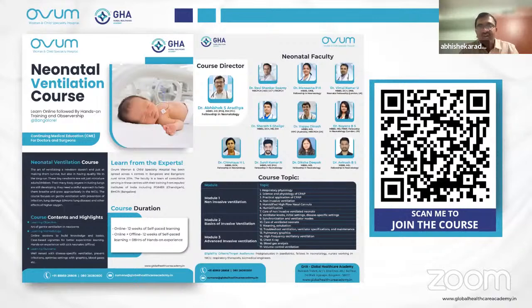The second question is on humidification. Sneha asks, what are the troubleshooting steps in humidification? Despite everything, sometimes it won't give the appropriate temperature. What's the role of heat compensation? Most of the time you are using auto flow nowadays, and you have to ensure that the flow is constant. So you need to keep that jar high up so that the water is continuously flowing. The distilled water bags which you use should be high up, and there should be air venting so that continuous water is there up to the optimum level in the humidifier chamber. A low level or high level of water in the humidifier chamber does not give you adequate temperatures.